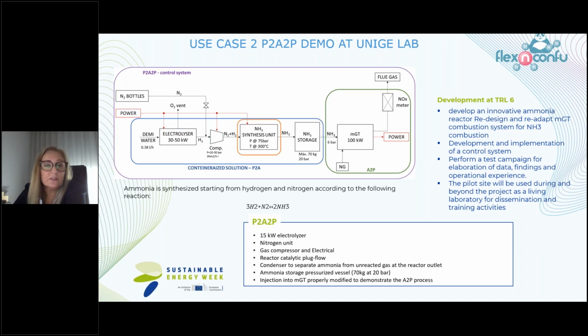The ammonia synthesis occurs in a catalytic plug flow reactor, and the ammonia storage holds 70 kilos at 20 bar. The injection into the micro gas turbine will be properly modified to burn ammonia, and a NOx analyzer will be installed to measure NOx gas emissions.